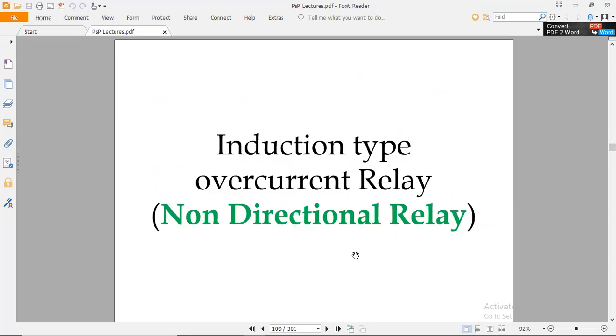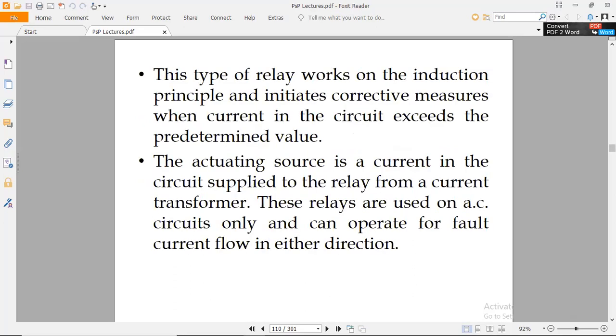Another category is the induction type overcurrent relay, which is the non-directional relay. This type of relay works on the induction principle. The induction principle is this: if there are two coils, and you provide supply to the primary coil, an induced EMF is produced in the secondary coil near the primary. The relay initiates corrective measures when the current in the circuit exceeds the predetermined value. The predetermined values are the values provided by the user.